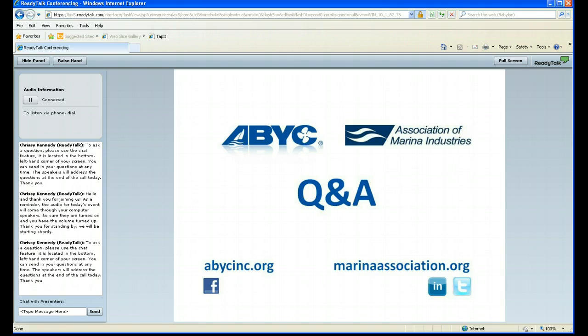And with that, I'm going to start fielding some questions. Chris and Gary, I do have a load on the list here, so I'm going to start with a couple. This one was interesting. It was about grounding conductors and how they're handled on the dock. The question is, what does the NEC state regarding the installation of grounding conductors on the dock? Is daisy chaining the grounding conductor acceptable? The person who asked believes that daisy chaining the grounding conductor on the dock exposes multiple slips to the possibility of allowing stray current in the water. Would either of you like to comment on that? The code does allow for daisy chaining of the grounding circuit. Typically, it's going to go back to a single source, whether that be an enclosed circuit breaker or a panel ground, and then that ground is run to shore in most locations. But it does allow for that ground to be looped together.